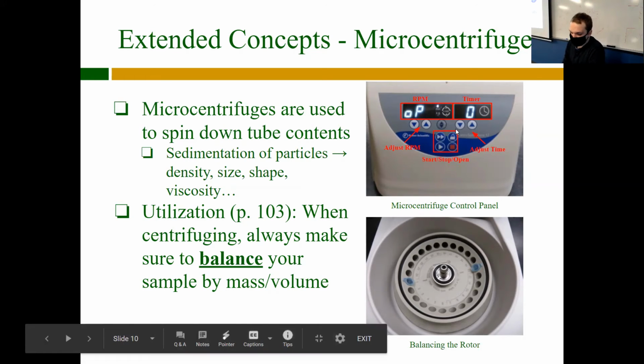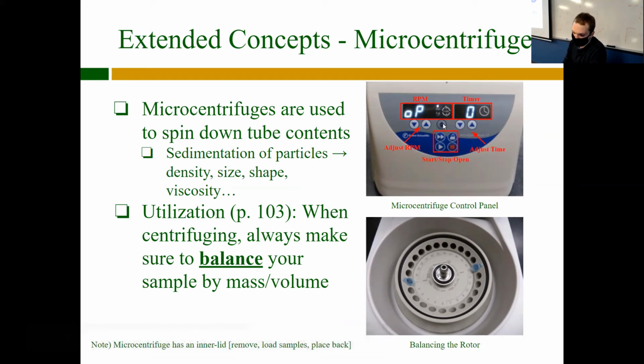I included a picture of the control panel. This is the RPM. There is a button right here that changes the units. Typically, it's just set on minutes minus, so that's just RPM. Get that at 14, that's times 10 to the third, so 1,000, so 14,000 RPM. So yeah, make sure it's set to that because typically all the procedures that we're working with use RPM. And then these are the buttons that adjust what the RPM is set at. Typically, we're working with 14 to 15. Maybe if you're just trying to mix something up a little bit, you'll go down to 8. It just depends on what you're working with.